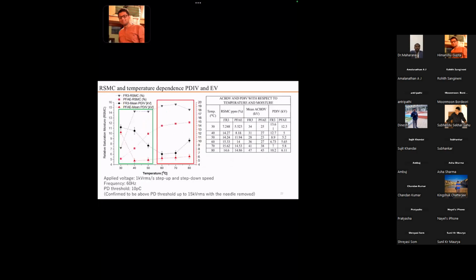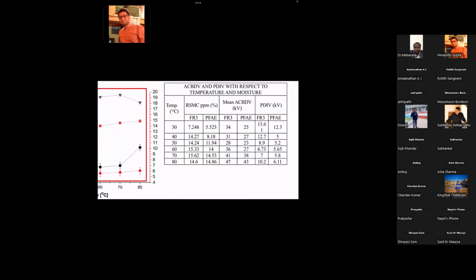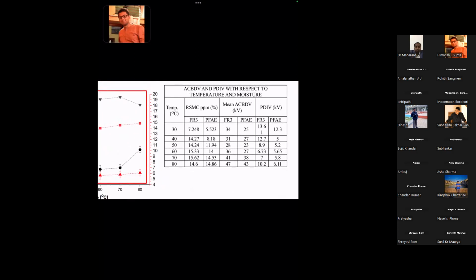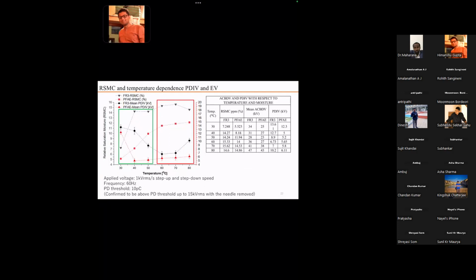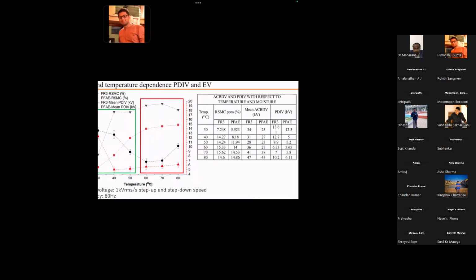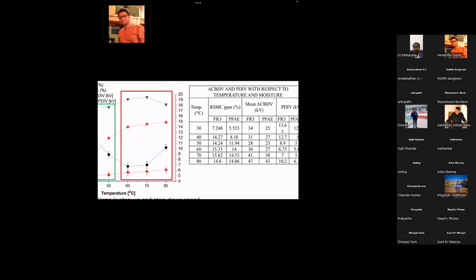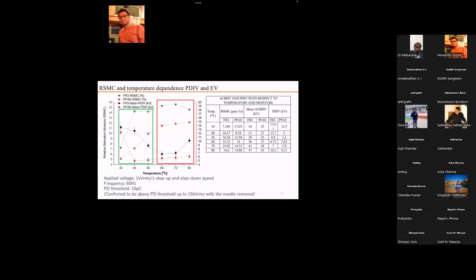Here we expected a result similar to the AC breakdown voltage. Up to 50 degrees the partial discharge inception voltage, and beyond 50 degrees the partial discharge inception voltage with respect to the relative saturation moisture content, was addressed. If you see from the table, as we increase the temperature, let me tell everyone, the relative saturation moisture content was up to 15%. Here we have considered up to 15%, not beyond. You can see the relative saturation moisture content in ppm is limited to 15% for both cases. Beyond 15% we have not done; we have done it in the later slides.